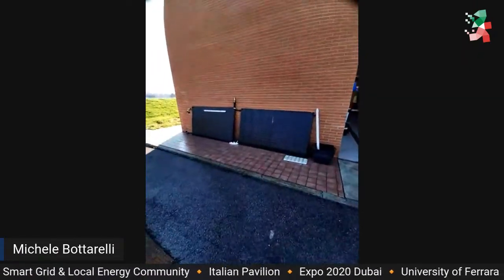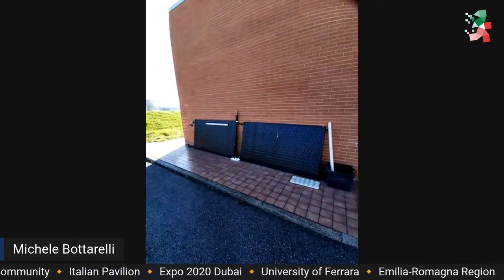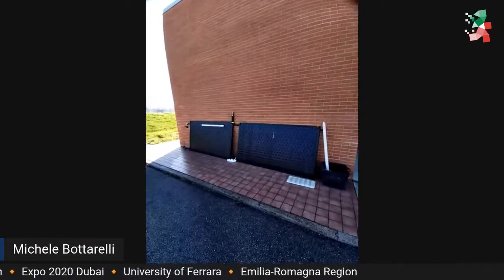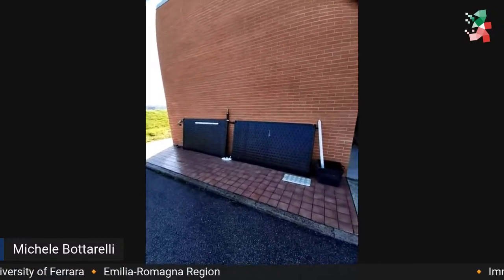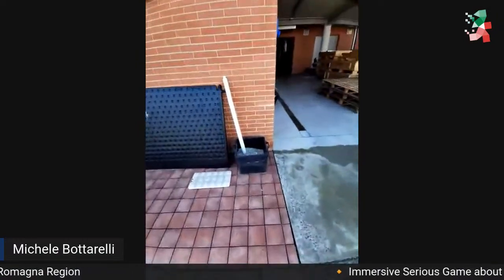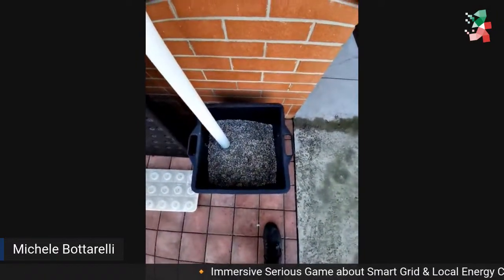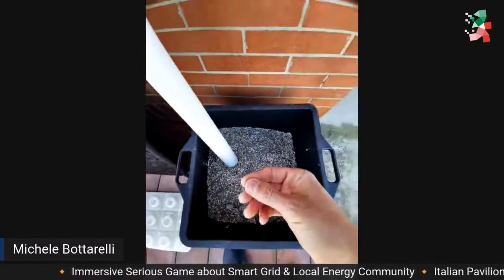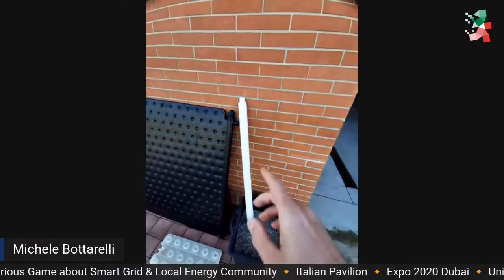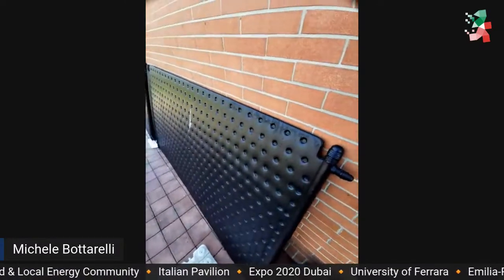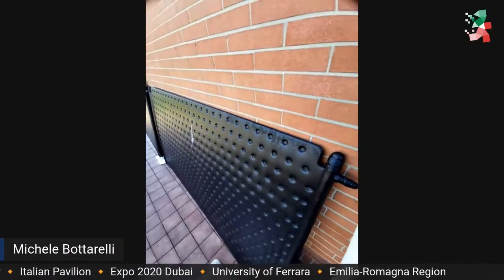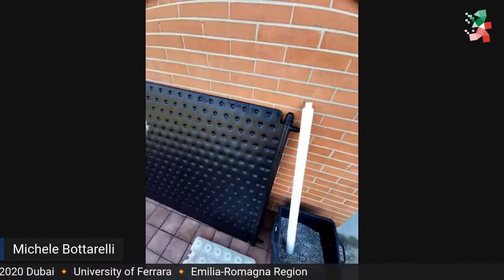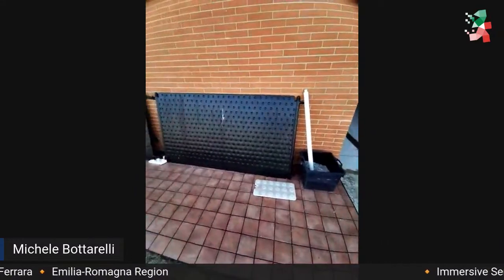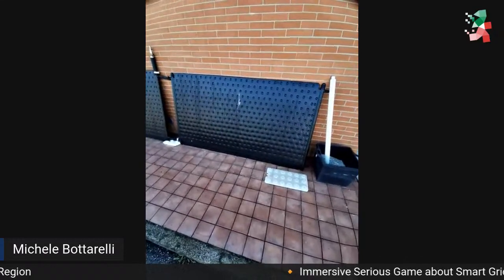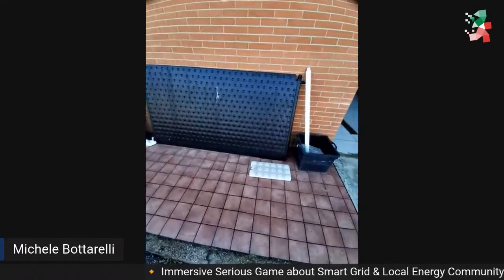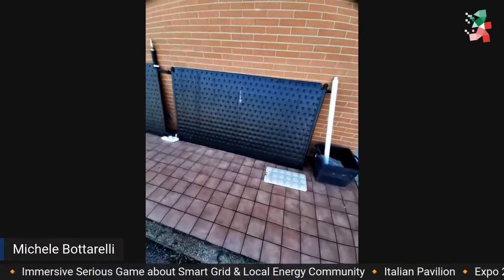Here you can see our flat panel used as a ground heat exchanger, installed 2.5 meters deep in the soil and backfilled with sand. Here is the sand with the granules, and here is the tube installed in the trench along with the ground heat exchanger. The trench is very narrow, only 40 centimeters, with a depth of around 2 to 2.5 meters.